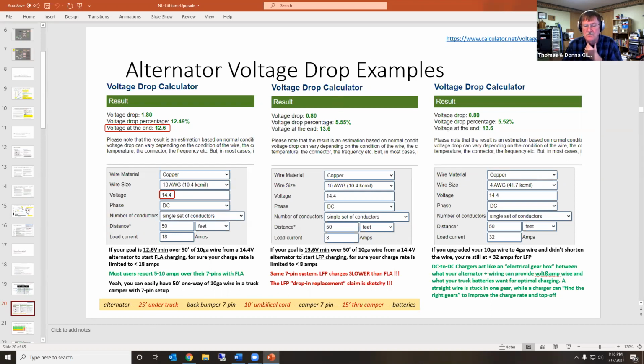The second thing was, imagine your goal is to at least hit that 13.6 volts minimum you need to start charging lithium batteries, but you had your same 10 gauge wire setup. When you run the voltage drop calculator, if you're putting an 8 amp load on this length of wire, at 8 amps you're going to be seeing 13.6 volts coming off the end of the wire. We know this is the point at which lithium just barely starts charging. So in a roundabout way, with a traditional 7-pin setup, we're basically limited to charging at less than 8 amps by definition.